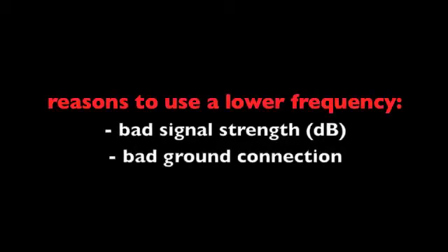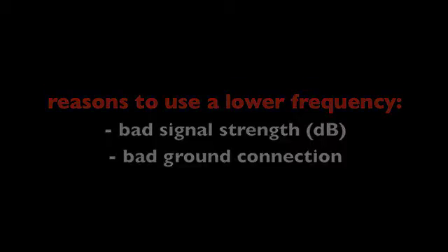A low frequency might not work if the line is buried deeply, giving you a weak signal, or if the pipe is damaged, meaning the signal is grounding prematurely.